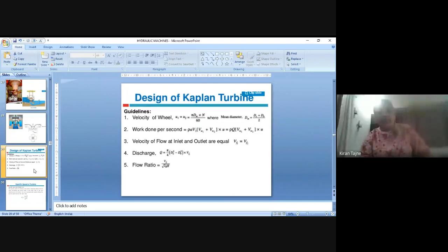So specific speed of the turbine is the speed at which a turbine will run when developing unit power under a unit head. Okay. So when the turbine runs developing unit power under unit head, that speed is known as the specific speed. So the formula is given: Ns, the specific speed, is equal to N root P by H to the power 5 by 4, where P is the power and H is the head of the turbine.